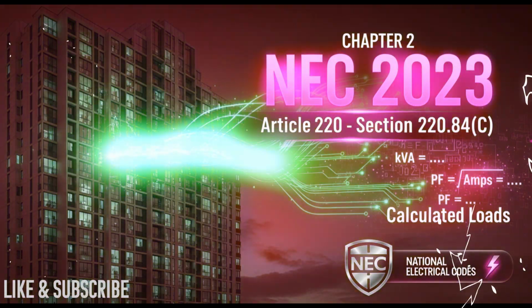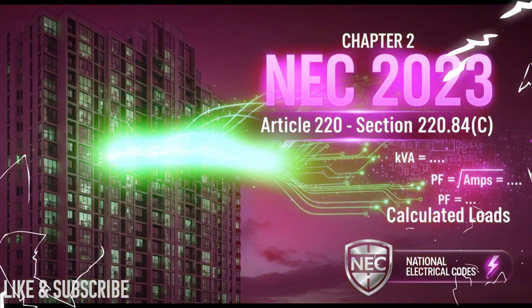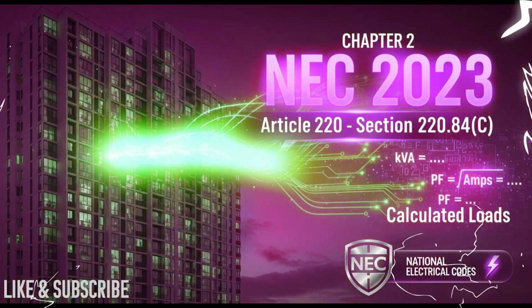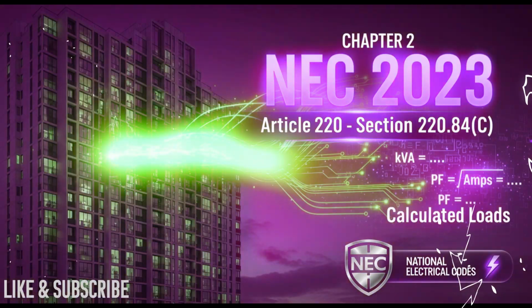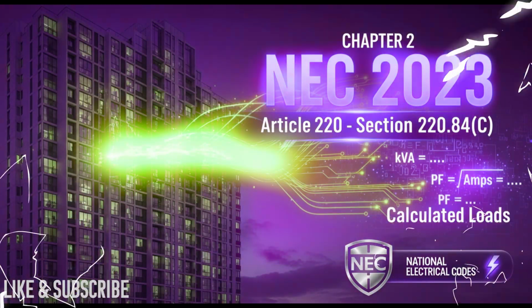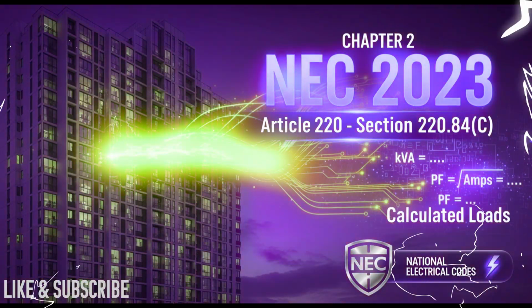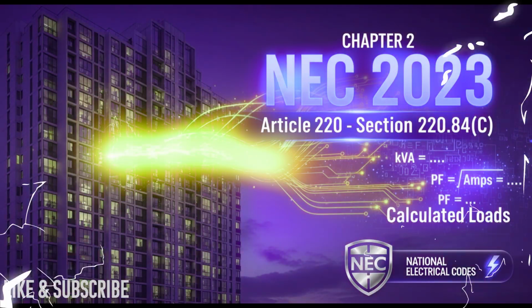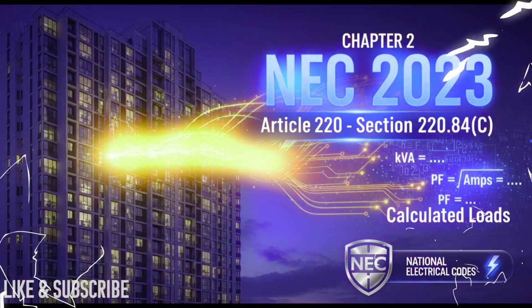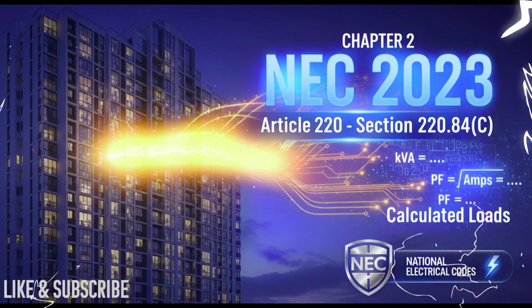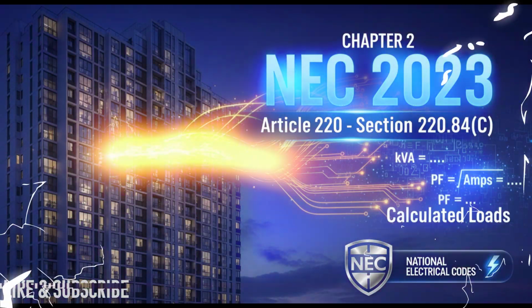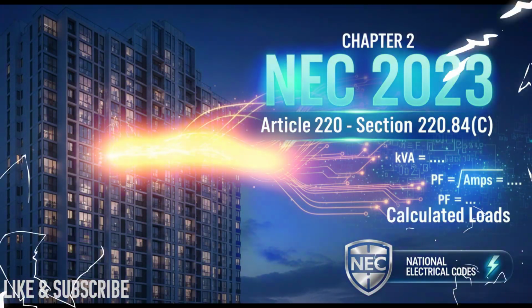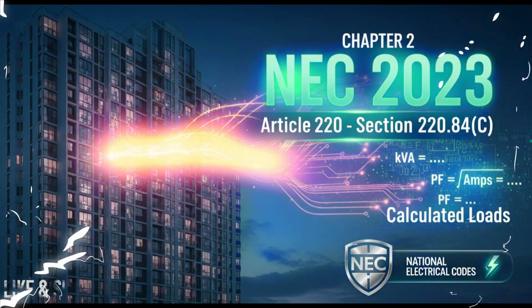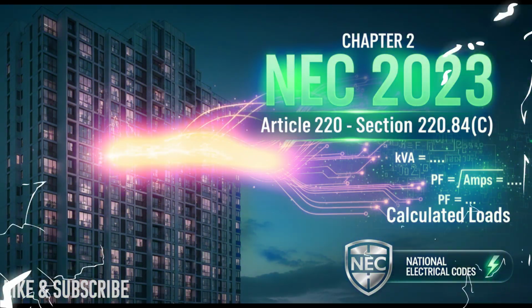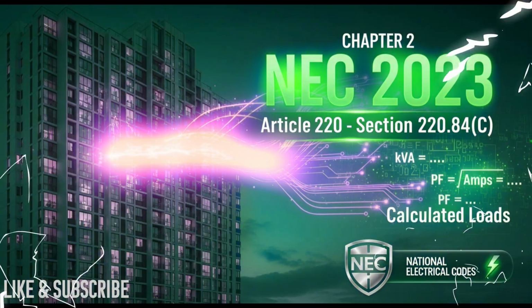So it's purely based on the size of the living space. Floor area dictates this base load. Exactly. 3 VA per square foot. But hang on, let me push back on that a bit. I mean, almost everyone uses super efficient LED lighting now, right? Which draws way less power than the old incandescent bulbs or even fluorescents. Isn't 3 VA per square foot kind of wildly conservative? Does that force builders to oversize things?